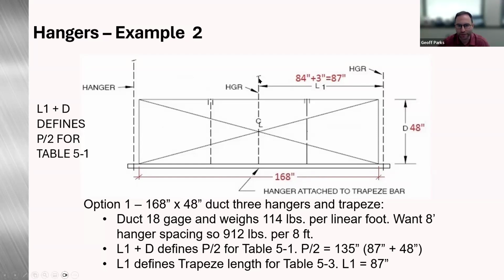So what we can do is take this L1, which is going to be half of our 168, plus our dimension from the hanger to the duct, which for this example is 3 inches. So this new L1 dimension is going to be 87 inches. This L1 now defines our half perimeter to size our hangers from table 5-1. And the L1 dimension also defines our trapeze length to size from table 5-3.